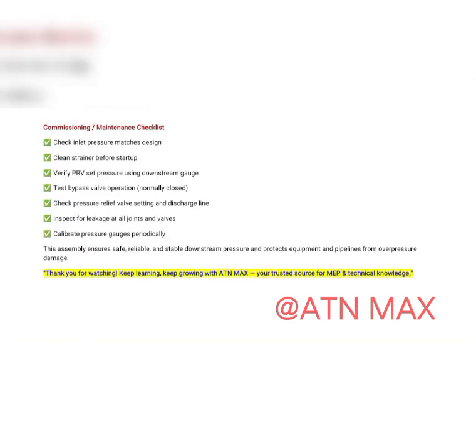Commissioning/maintenance checklist. Check inlet pressure matches design. Clean strainer before startup. Verify PRV set pressure using downstream gauge. Test bypass valve operation, normally closed. Check pressure relief valve setting and discharge line. Inspect for leakage at all joints and valves.